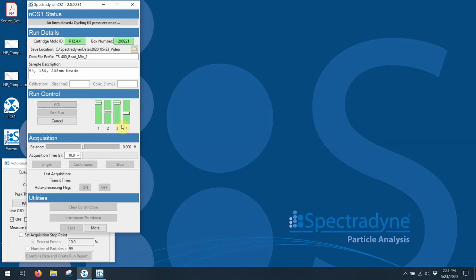At this point, the system runs through the pressures a few times in order to make sure that everything is stable inside of the cartridge. The hissing sound you hear is the system lowering from the priming pressures, which are higher to the actual measurement pressures, which are lower. And once it's finished doing this, you'll see all the monitors will drop down to zero and we'll begin the acquisition.